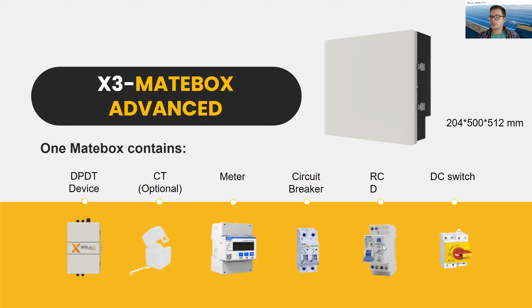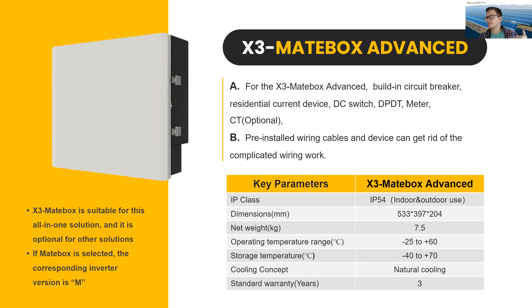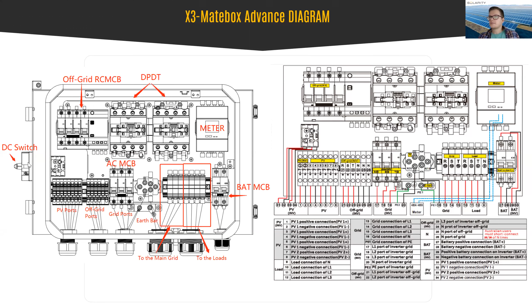The Matebox for the three-phase solution is obviously bigger because it requires more space to install all the required devices, but it's still not heavy. It's just 7.5 kilos, and it can operate in extreme temperatures from -25 to +60 degrees. So it can be located outside as well, together with the energy storage system and the hybrid inverter. So as you see, as I mentioned before, the Matebox is a little bit bigger. You can find the energy meter here. The DPDT device is also bigger because it's the three-phase solution. And of course, it should have the same equipment as the battery breaker, the AC breaker, and the DC switch.